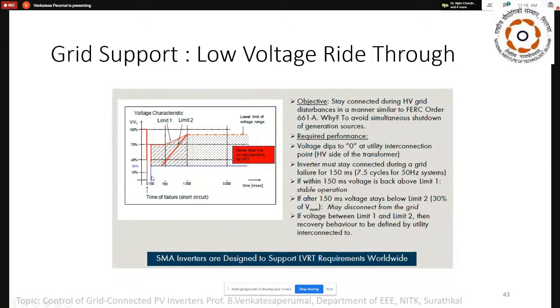After 150 milliseconds, if the fault clears and the voltage goes to 70%, then it should work normally, and then it should go to 90% within that limit. Or up to 650 milliseconds, it will stay at 30% and then start rising. That is also normal. So we need not disconnect the system.